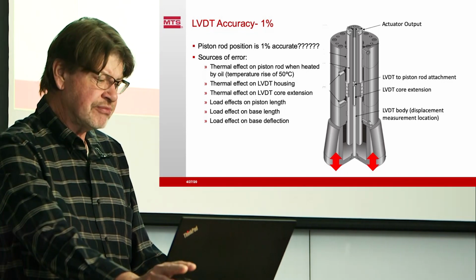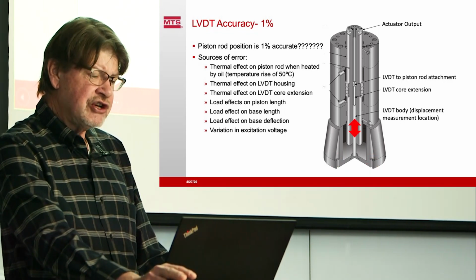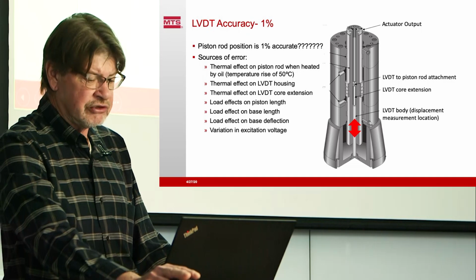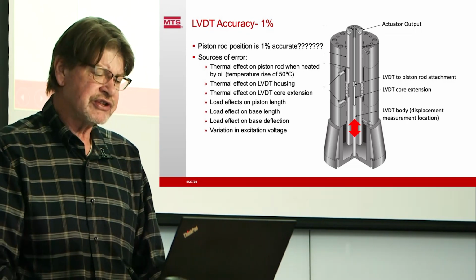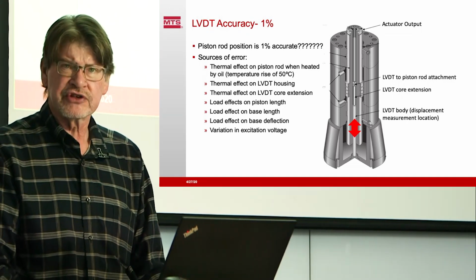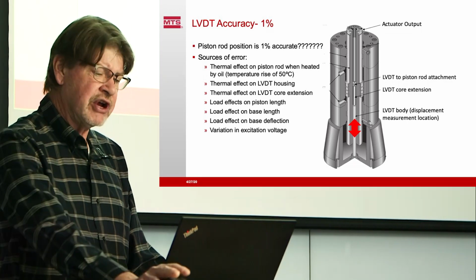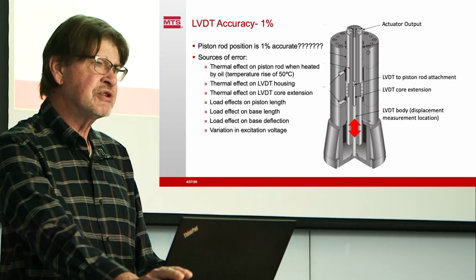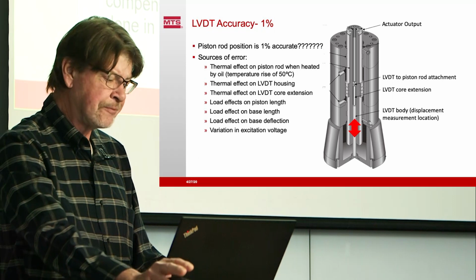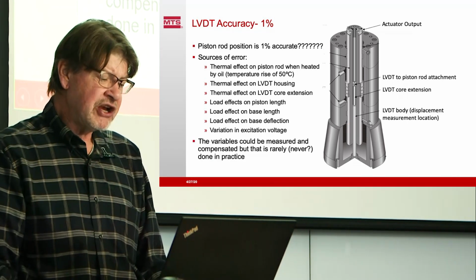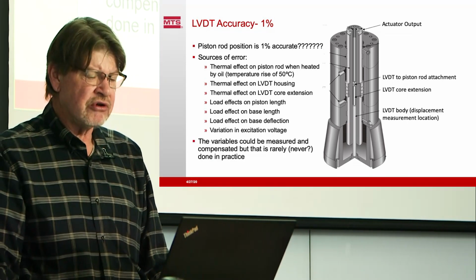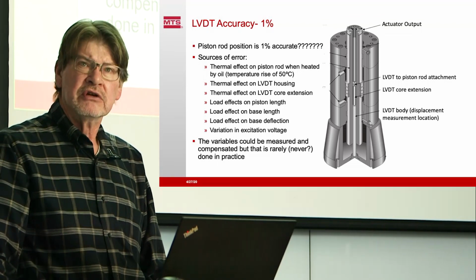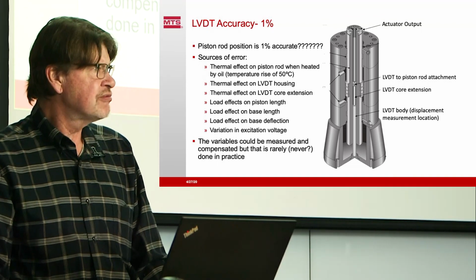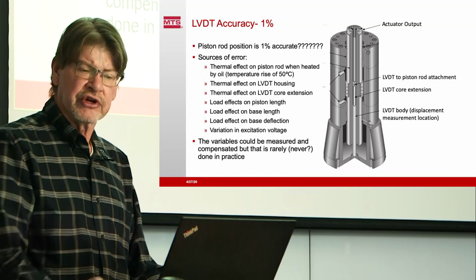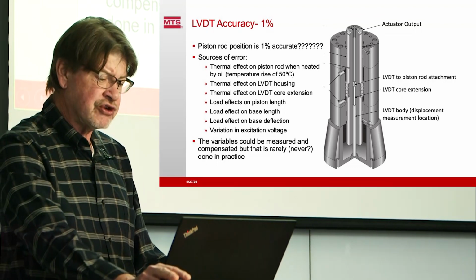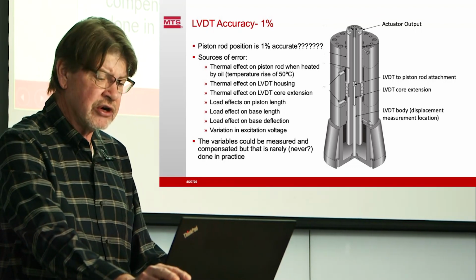So all of those things mean that the variation in the output of the actuator can be a little different than exactly what we're measuring. There's other things as well. Variation in excitation voltage is another potential source of change or error. These variables could be measured and compensated, but I don't know of anyone who has ever done that. Rather, if they need a really critical measurement, maybe they go to a remote transducer or an extensometer or some other way to do the measurement. Otherwise, most people just ignore errors like this.